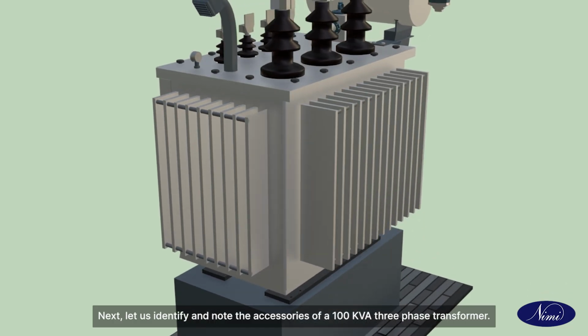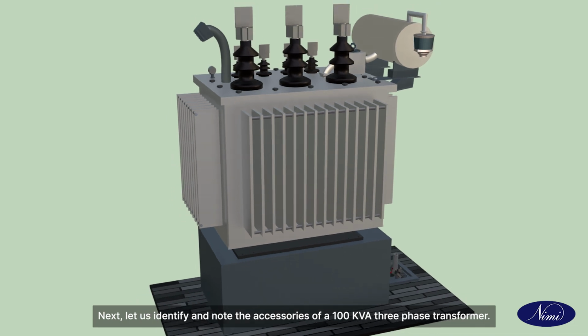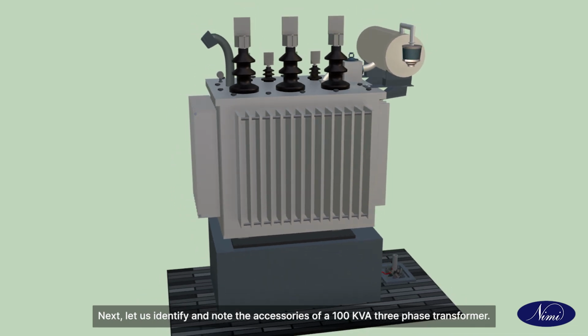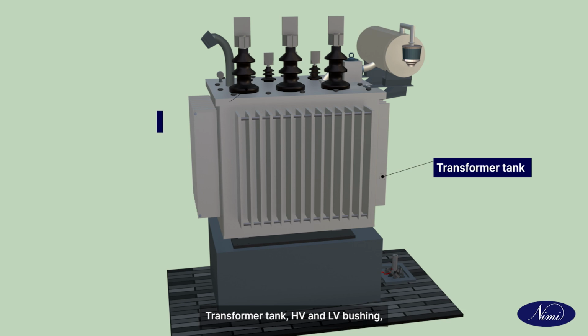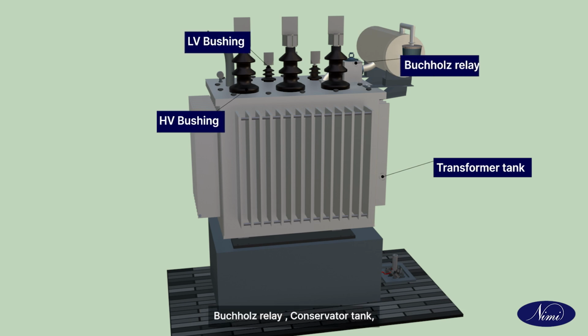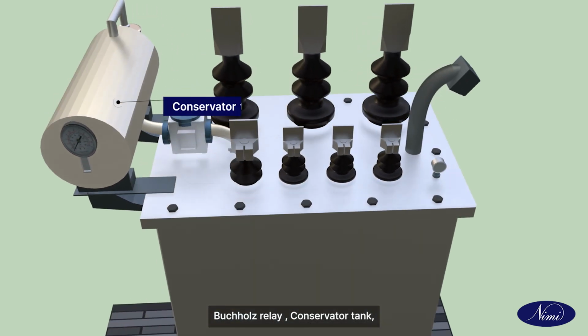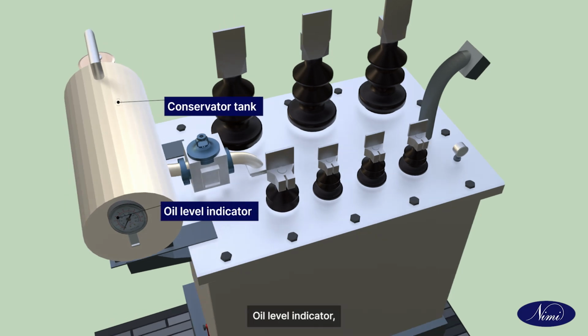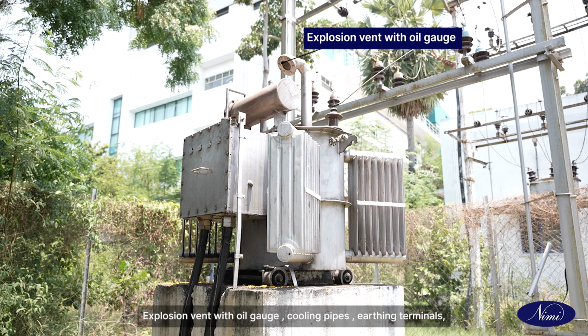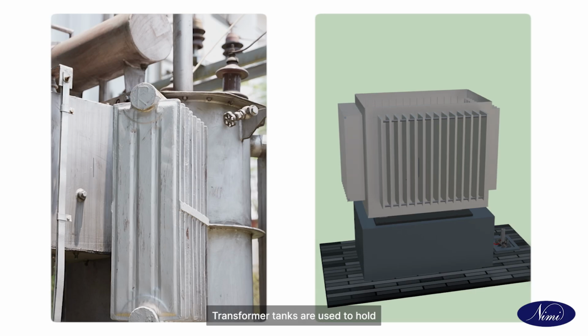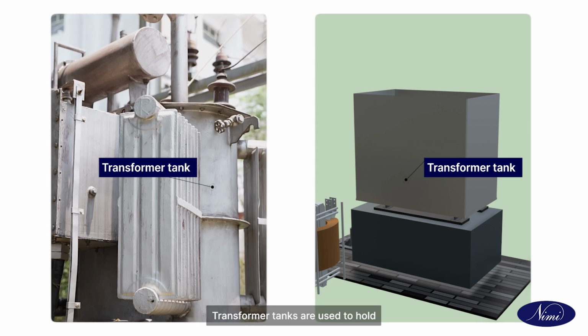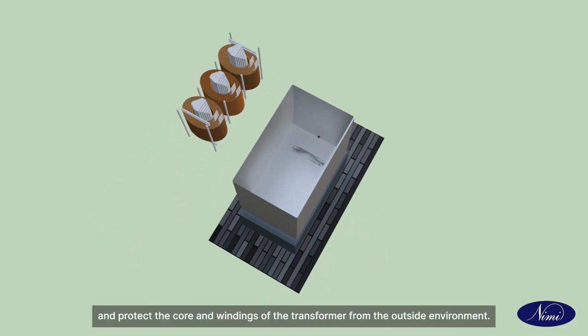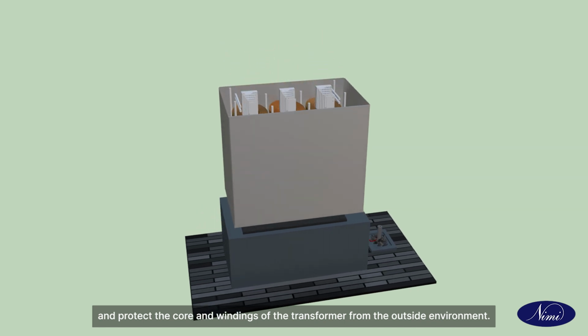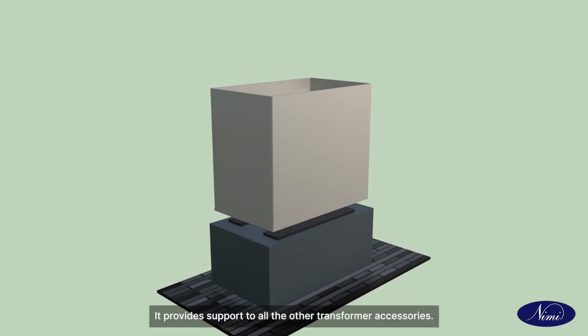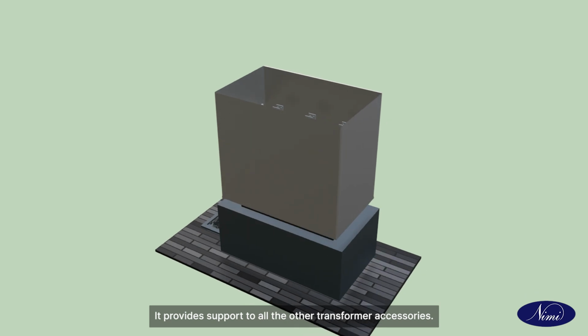Next, let us identify and note the accessories of a 100 kVA 3-phase transformer. Transformer tank, HV and LV bushing, Buchholz relay, conservator tank, oil level indicator, breather, explosion vent with oil gauge, cooling pipes, earthing terminals. Transformer tanks are used to hold and protect the core and windings of the transformer from the outside environment. It provides support to all the other transformer accessories.